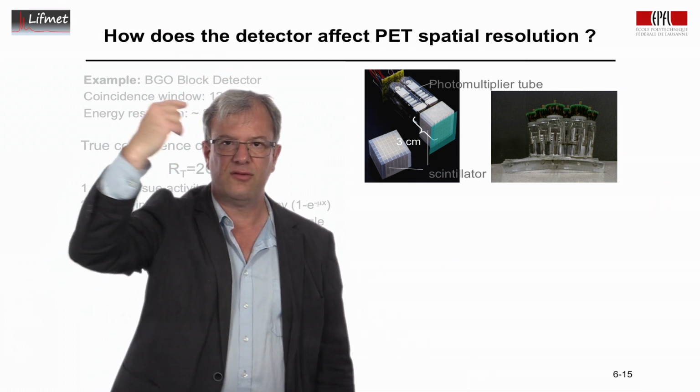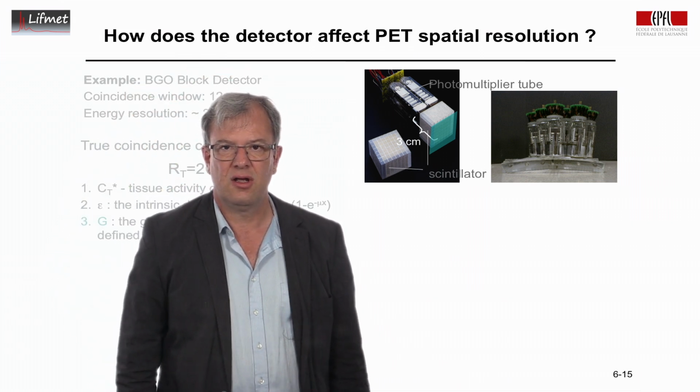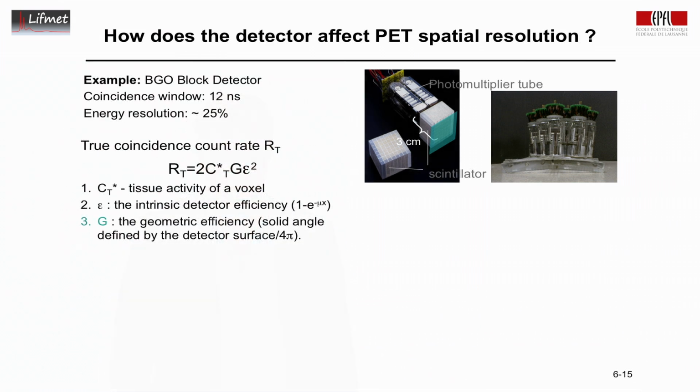Think of it this way: all the X-ray pairs go in all directions. We have a detector up here. This detector will only see a small percentage of the entire spherical surface at its location, and these are the maximum counts that you can have. It's the geometric efficiency. To give you an idea, if the detector efficiency of this detector is, let's say, 90%, since we are detecting a photon pair, we have to also consider the detector efficiency on the other side.